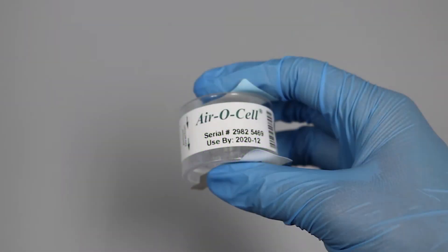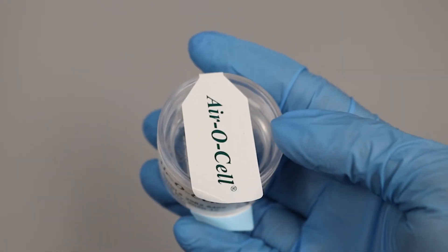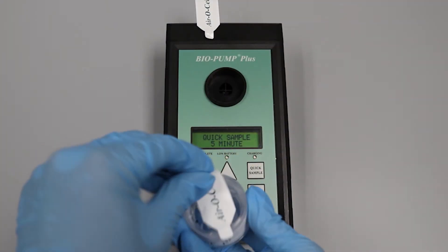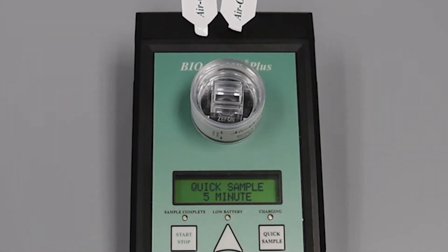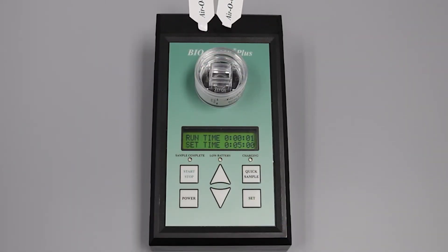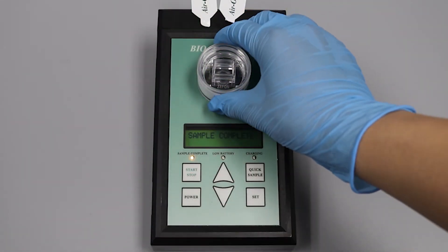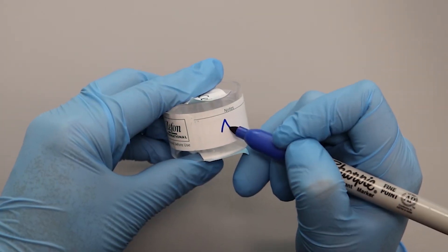After you've chosen the appropriate sampling time, take out an Air-O-Cell cassette, verify the use-by date on the cassette, and make sure that the security tape is attached properly and undamaged. Take both security tapes off and retain for resealing. Place the Air-O-Cell cassette on the pump with the rectangular port facing upwards. Press start to begin sampling. Once completed, the pump will beep, the display will show sample complete, and the yellow sample complete light will turn on. Remove the cassette gently by pulling upward. Seal the cassette with the security tape. Label the cassette with location and date, then record the cassette serial number, location, and date on the chain of custody form.